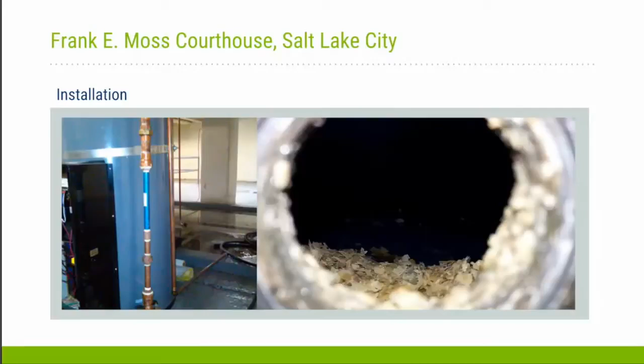In the past, when we had a failure with one of the elements in the water heater, typically 4 or 5 elements would fail at the same time, and when we pulled them out they were in bad shape. Now, typically if one element fails, it's only one, and they last much longer, almost a year now, where we were replacing them almost every 6 weeks before.